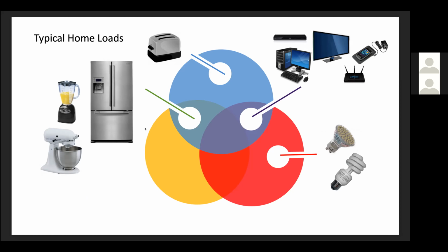As far as some of your other home appliances, a refrigerator, most especially, has a characteristic of a continuous load, which is kind of like its running watts. And when that compressor cycles, it will have characteristics of inrush. That compressor will have quite a bit of surge. It could be quite a bit more than its running watts, especially for today's energy efficient refrigerators. Other home appliances or consumer electronics would have characteristics of both that continuous load profile as well as the transient. These switch mode power supplies do introduce transients to the voltage waveform. And if they occur simultaneously, they have an additive effect and could trip the battery offline if it exceeds that 8 amp, 100 microsecond limitation.